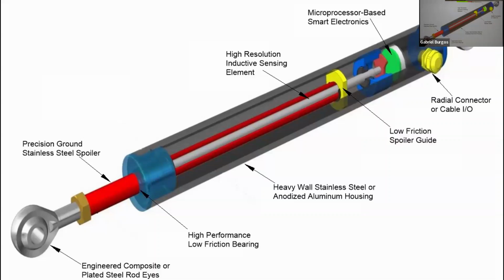This is a cutaway, and basically what it amounts to is this: you have a coil layer, single layer coil as a rule. I should point out something before I forget: LVDTs are typically operated at frequencies on the primary between 1 kilohertz and 10 kilohertz, sometimes a little higher. But they don't work at 60 hertz. So if you buy one, don't think you can plug it into the wall or into a little transformer and make it work — it's not going to work. Not enough iron. But they work from 1 to 10 kilohertz as the excitation.